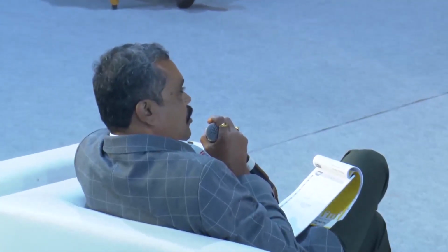Secondly, right now in industry, majority our LEDs and everything, many times some malfunction happens. A person from a CNC company comes and tells me, I want a separate earthing and I want a neutral earth voltage below 1 volt. What is this concept? An electrical apparatus which has a metal body falls in class 1, class 2 or class 3; there are 3 categories of electrical items. Class 1 is the equipment which needs earthing or equipotential bonding. Every class 1 electrical apparatus is able to work up to the nominal voltage between neutral and body. Meaning, even if the neutral to earth voltage is 230 volt plus 10%, the equipment is supposed to work.